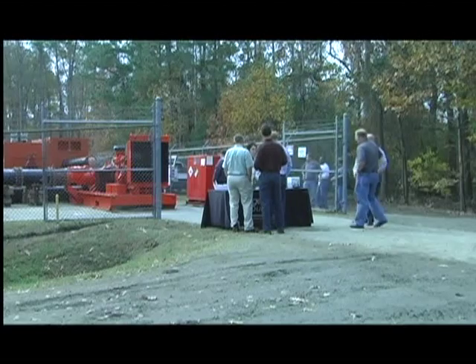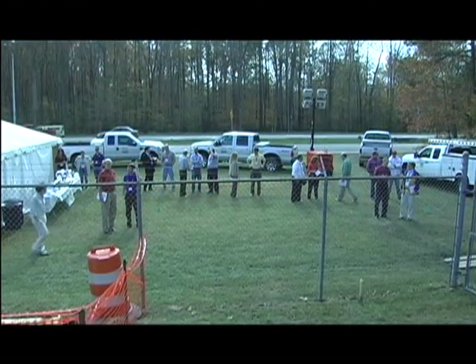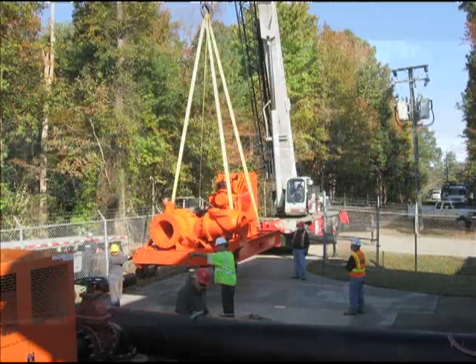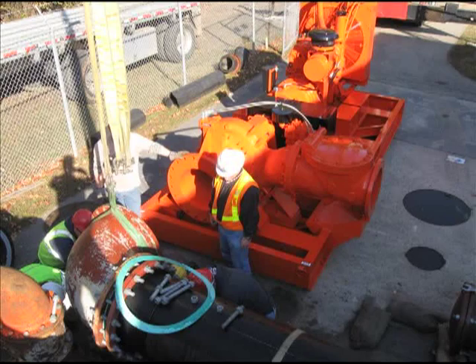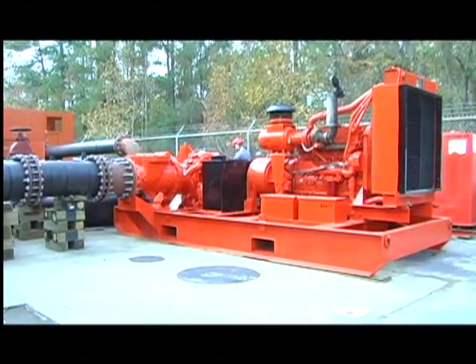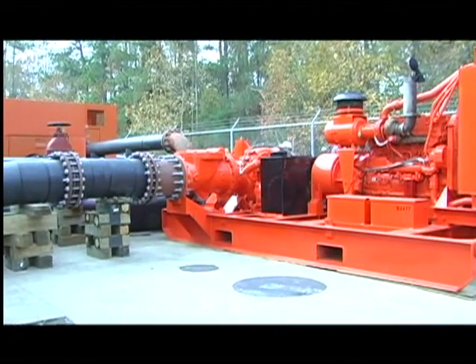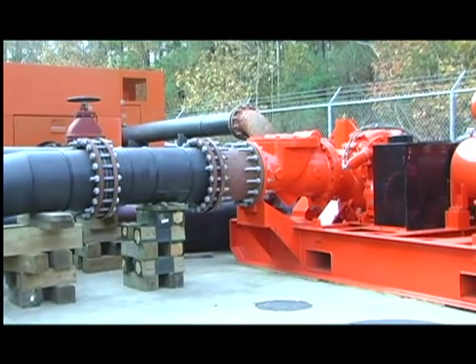This is Ships Corner Pressure Reducing Station for HRSD. What we're doing here today is putting in temporary diesel pumps that will bypass this station. The normal operation of this station is there are several municipal pump stations that pump into a common force main. That force main comes up to this Ships Corner pump station and then it boosts the pressure down to the wastewater treatment plant — it conveys the flow.